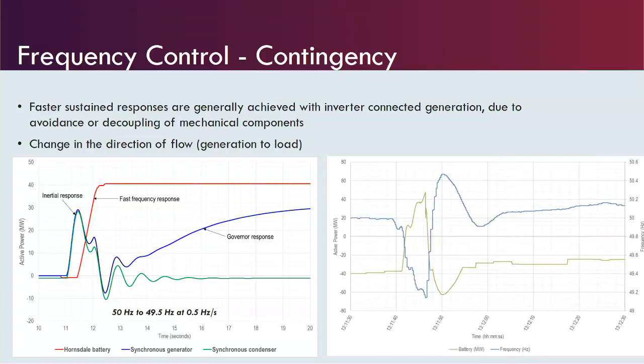Here we've got a not-too-great response of a synchronous generator on the NEM. It provides an inertial response - being a synchronous machine, it'll decelerate once the frequency starts to fall, pushing some power into the network. After a while, the governors will kick in, or should kick in, and start providing some real active power.